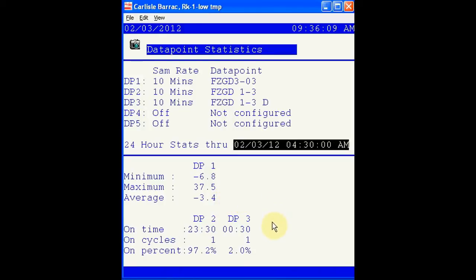The relays are listed here, including the refrigeration relay seen as DP2 and the defrost relay seen as DP3. This information tells us that the refrigeration relay was on completely in the last 24 hours except for the 30 minutes for defrost. There was one cycle indicating there is only one defrost programmed for this case, and you here will see on percentages for each relay.